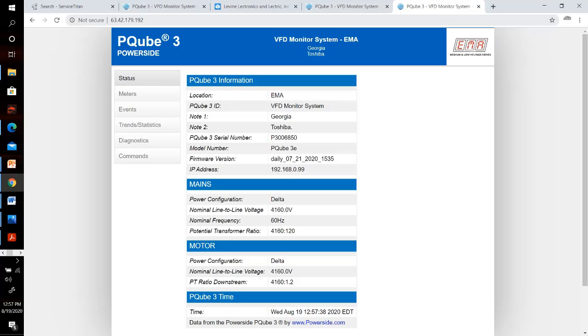Last question: what's the best way to predict a capacitor failure in a Siemens medium voltage power cell? That's a very good question. As the capacitor loses its capacitance - it's an electrolytic capacitor, and Siemens use electrolytic capacitors in their drive - the electrolyte loss increases, which happens due to the heating effect in the drive or ripple current in the capacitor.